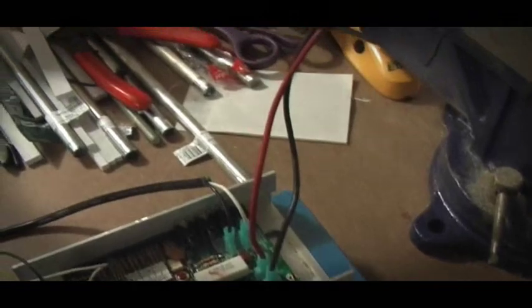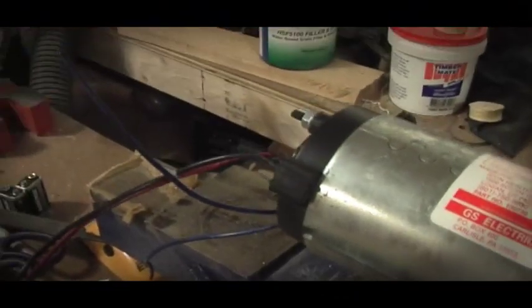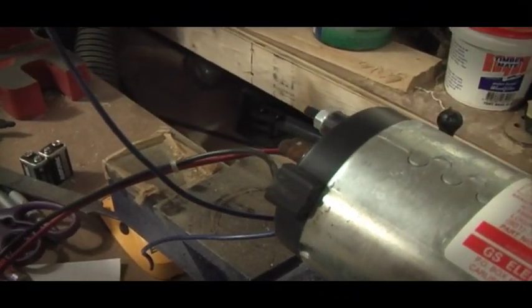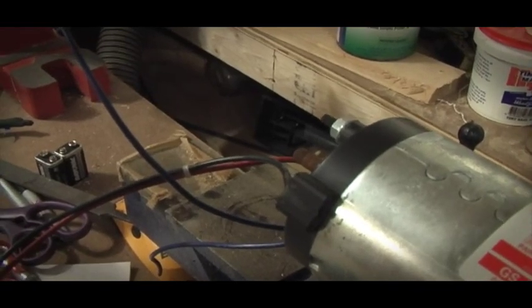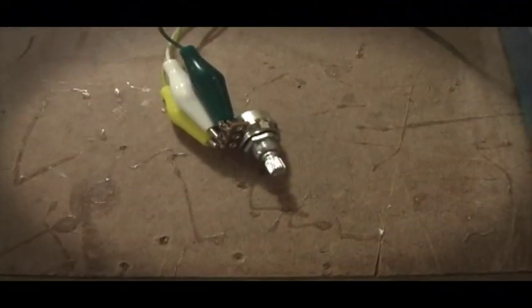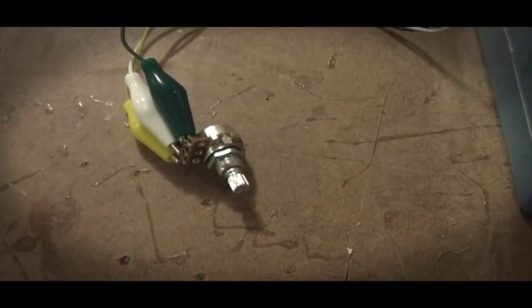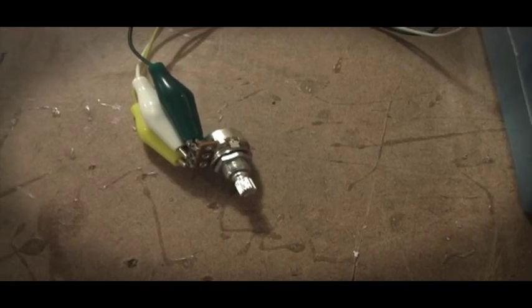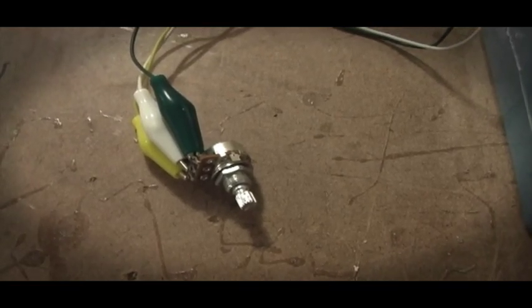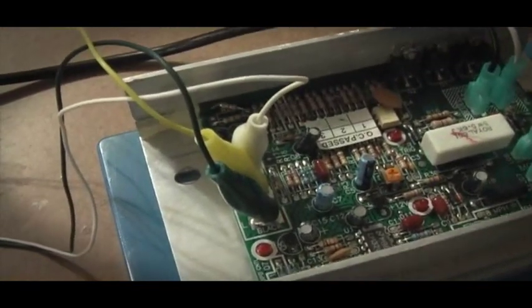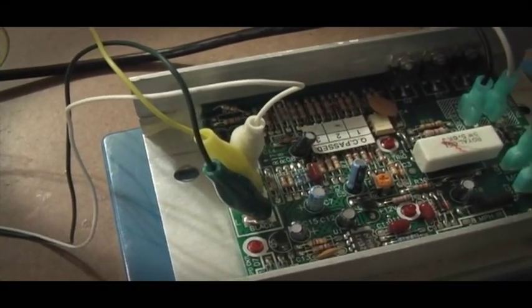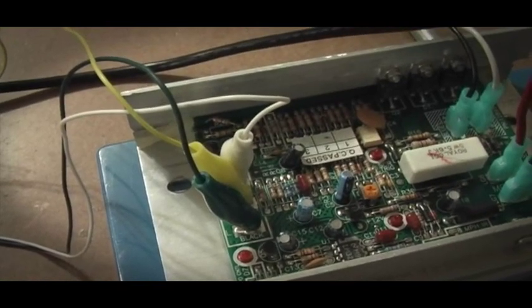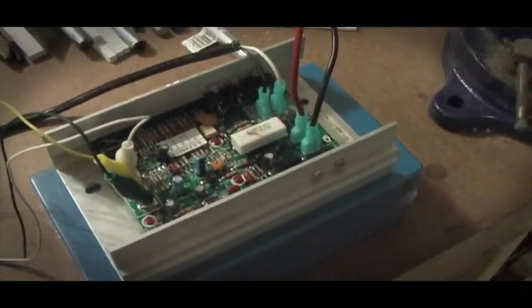We have AC line voltage, which is connected and ready to go. We have DC connection to the motor off the controller. I didn't hook up the thermal switch on this particular run just to eliminate it as a culprit should something not work properly. And then we have what I believe is a 250K linear taper pot hooked to the potentiometer terminals, which is going to control a 24 volt DC supply to the controller.